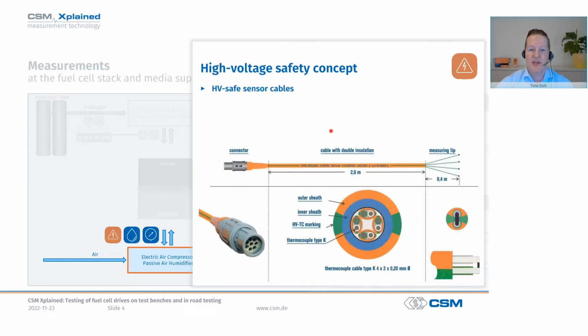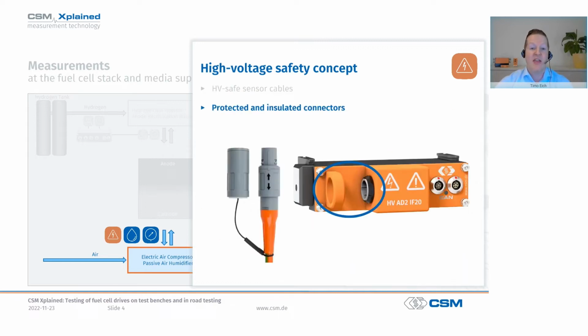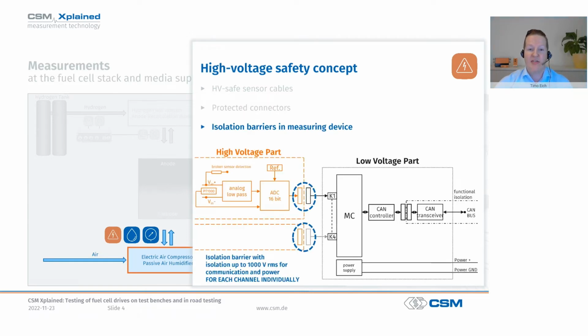This high voltage safety concept consists, amongst other things, of electrically insulated touch-proof cables with a very special structure that varies depending on the measured variable to be recorded. Then it also includes special high voltage safe and mechanically protected connectors. We see them here. And the core of this high voltage safety concept is a high voltage isolation barrier which must be provided for each measuring channel and which provides reinforced insulation according to DIN EN 61010. If you want to know more about this, just have another look in the first episode of CSM Explained in our archive on our website.